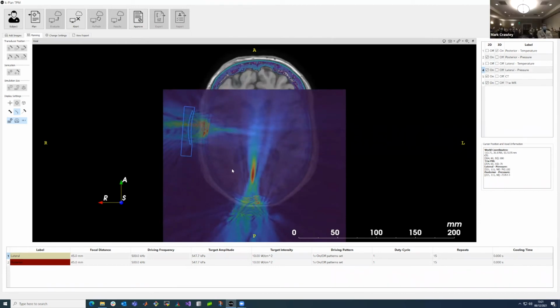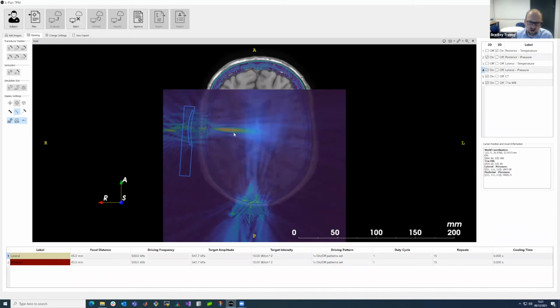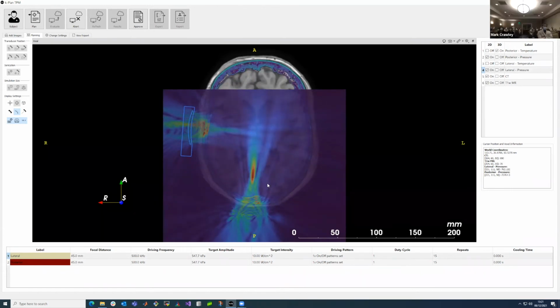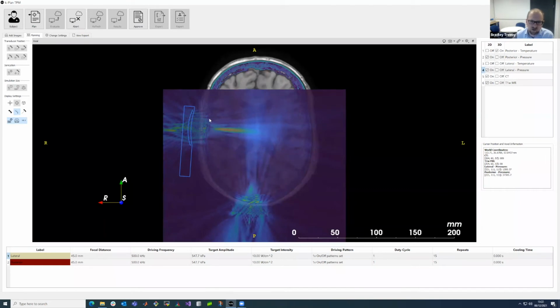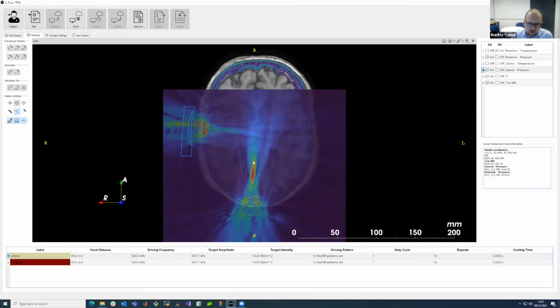This pre-planning, or understanding what the ultrasound field looks like inside the brain, is really important, both for safety and for targeting efficacy. If you want to deliver a particular intensity into the brain, you need to know on an individual basis how much of that energy is lost in the skull. And you can't just produce those numbers from a rule of thumb. Even knowing the skull thickness is not enough. You need to know something about the structure of the skull, which is built up of cortical and trabecular layers. So you really need individual information to help you locate your focus in the right brain region, but also to understand the intensity you're delivering and the safety profile.